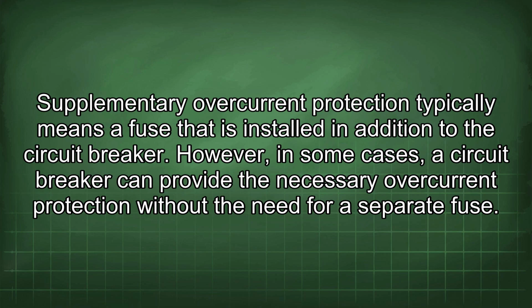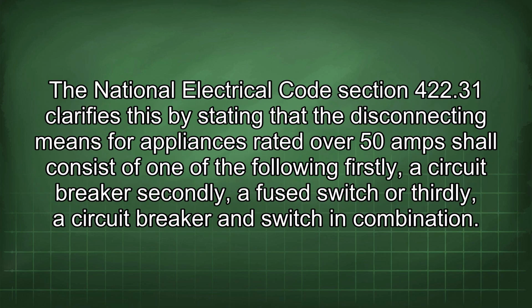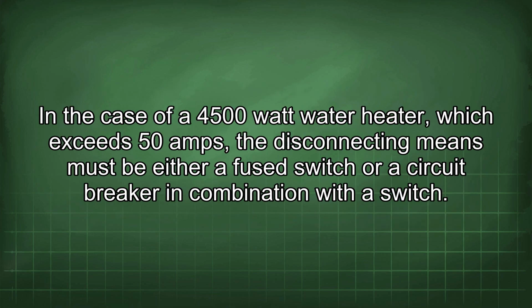However, in some cases, a circuit breaker can provide the necessary overcurrent protection without the need for a separate fuse. The National Electrical Code Section 422.31 clarifies this by stating that the disconnecting means for appliances rated over 50 amps shall consist of one of the following: firstly, a circuit breaker; secondly, a fuse switch; or thirdly, a circuit breaker and switch in combination. In the case of a 4,500 watt water heater, which exceeds 50 amps, the disconnecting means must be either a fuse switch or a circuit breaker in combination with the switch.